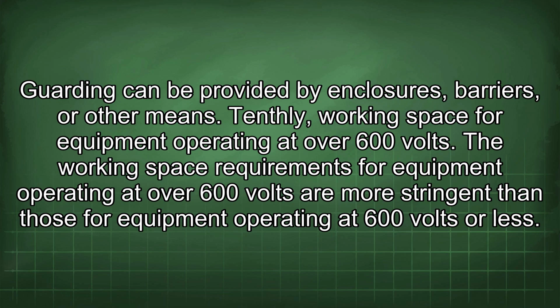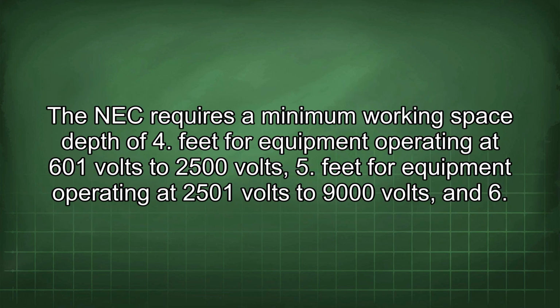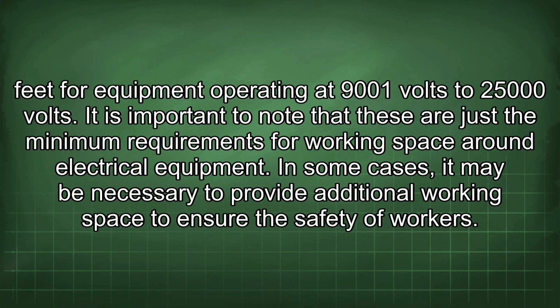Tenthly, working space for equipment operating at over 600 volts. The working space requirements for equipment operating at over 600 volts are more stringent than those for equipment operating at 600 volts or less. The NEC requires a minimum working space depth of 4 feet for equipment operating at 601 volts to 2500 volts, 5 feet for equipment operating at 2501 volts to 9000 volts, and 6 feet for equipment operating at 9001 volts to 25,000 volts.